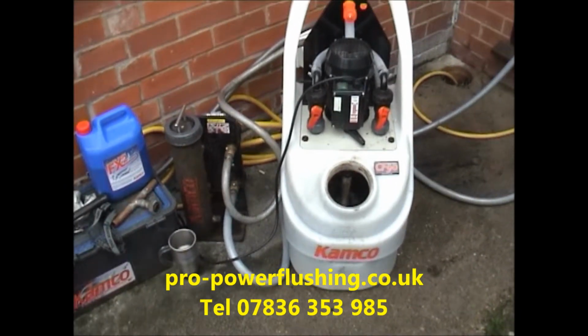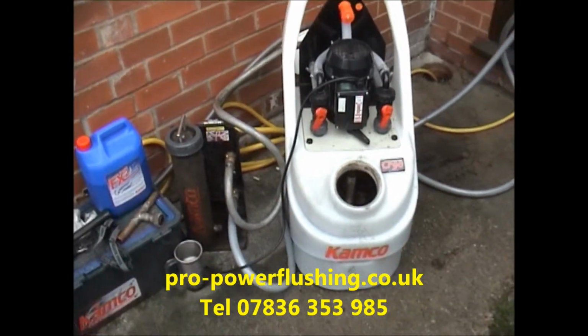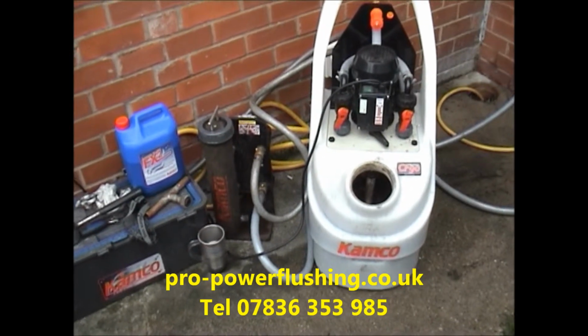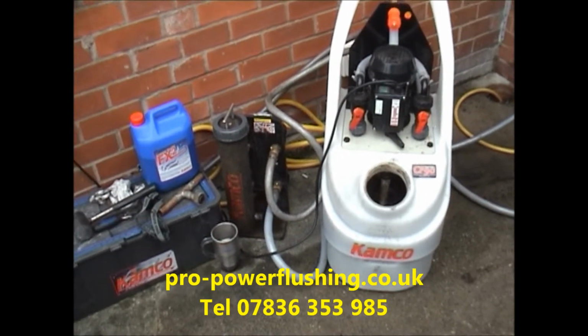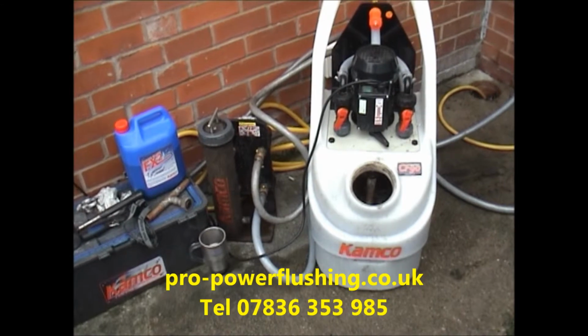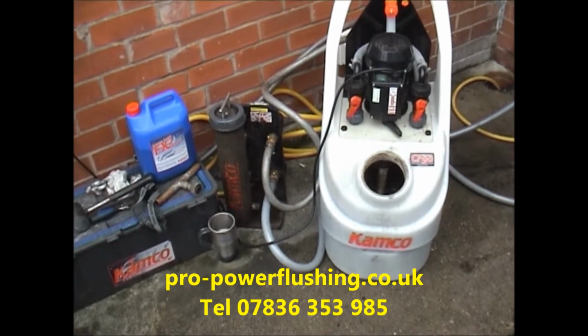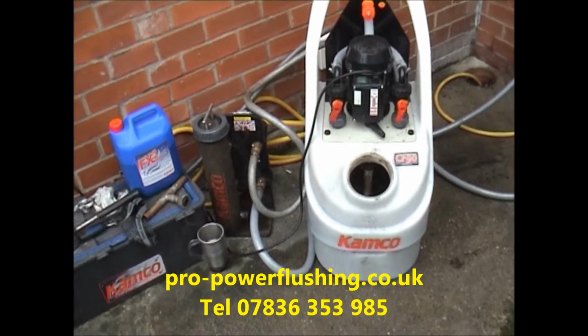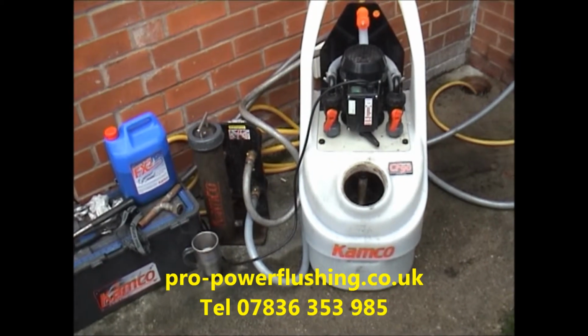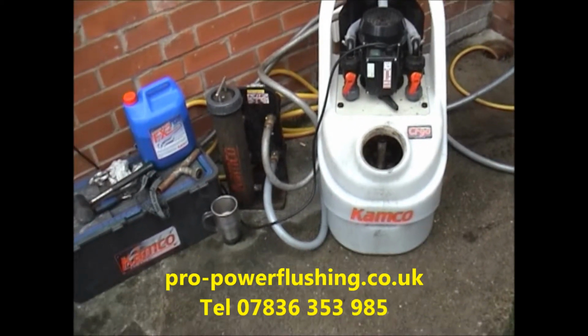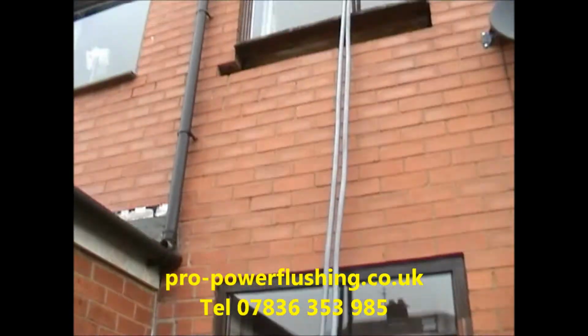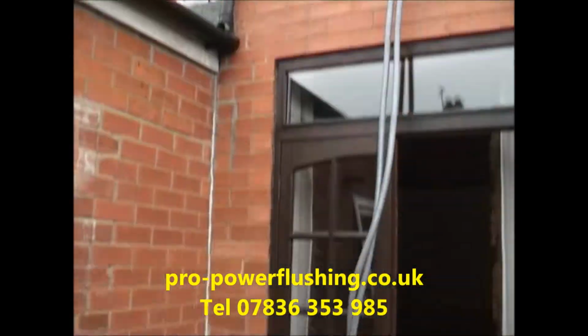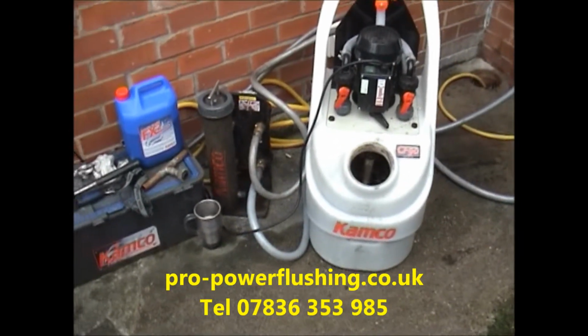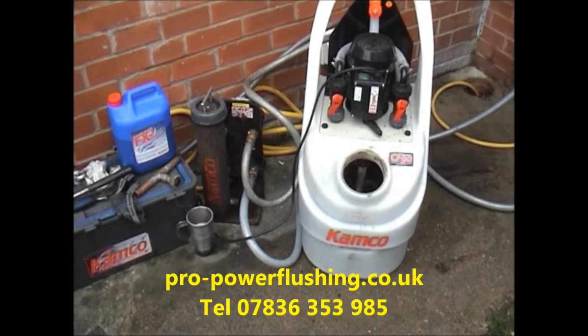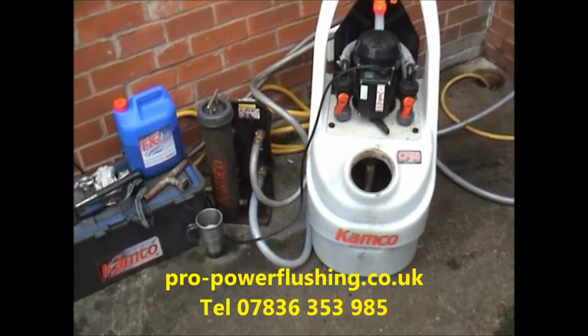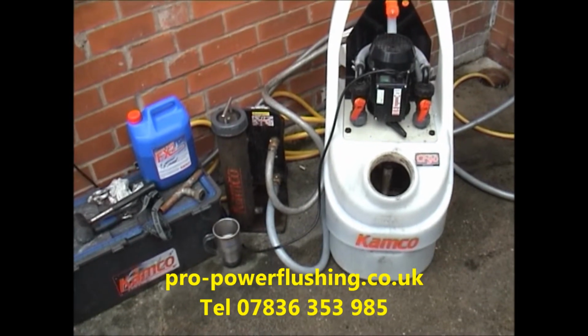We're doing a power flush today. The system is an open vented system, fairly old, probably 25-30 years old, with a hot water cylinder and pump in the loft space, which isn't ideal. We've had to go up through the house and into the loft with the hoses, and we've connected onto the pump housing, because that way we're getting a really good flow through the system.